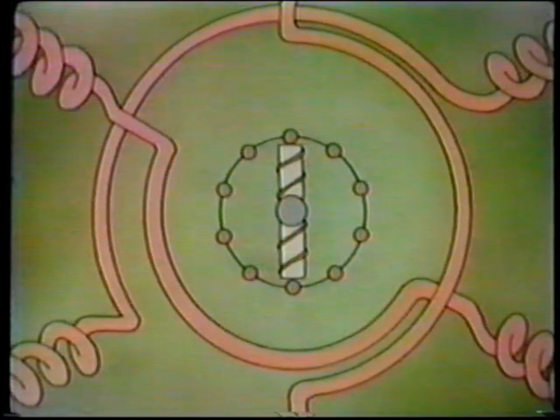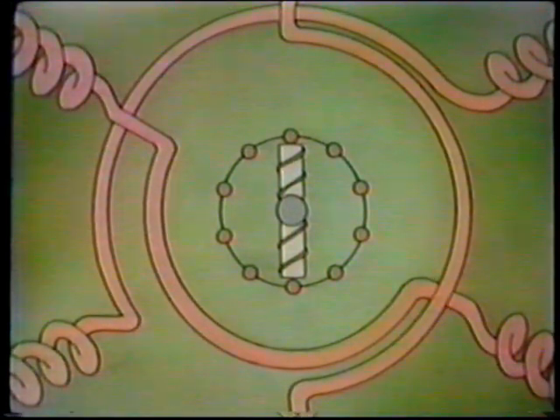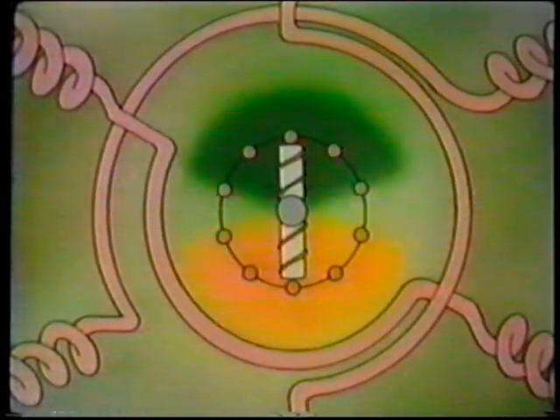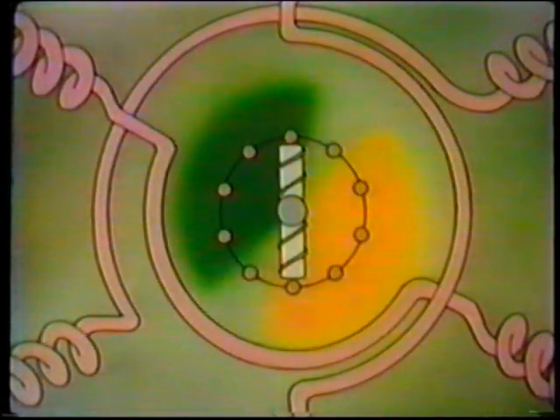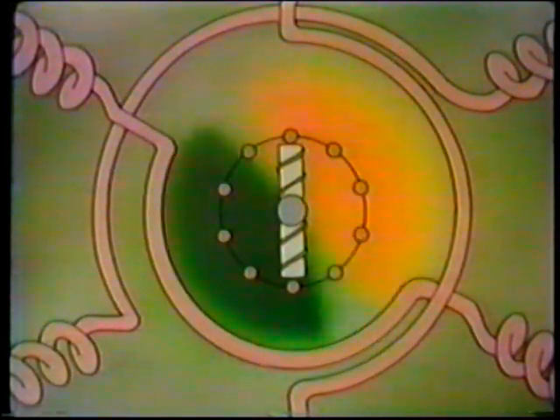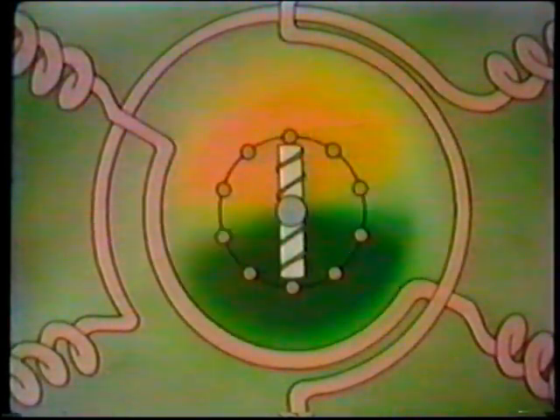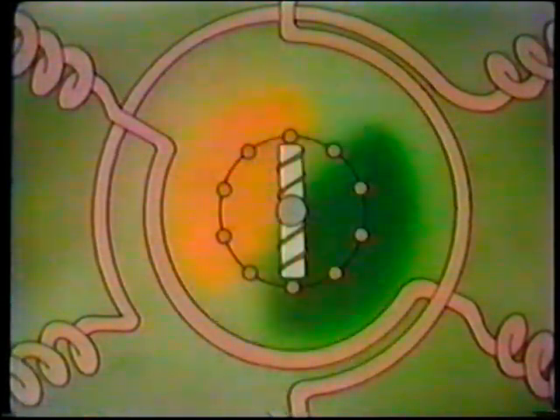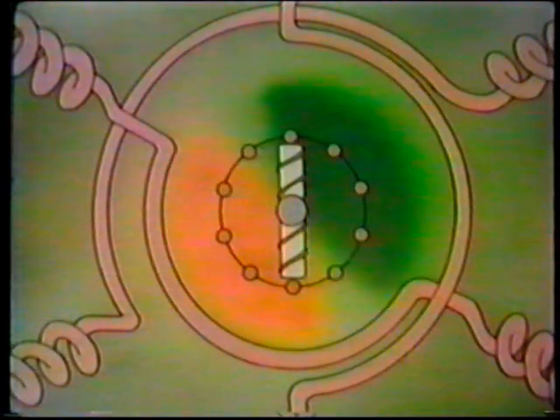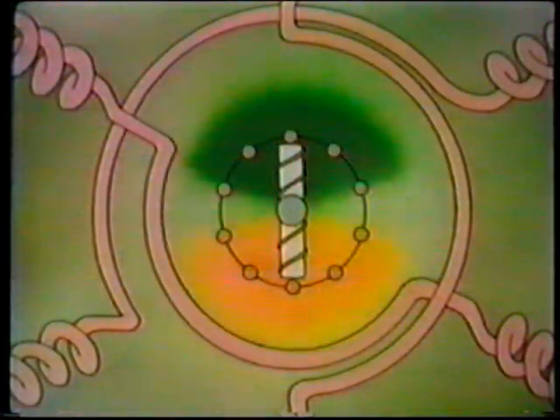Here's a simplified version of a rotor for a synchronous motor with amortisseur bars on it. When the motor is first started, the stator field immediately rotates at synchronous speed. The rotor, however, is unable to lock in with the stator's rotating field. But relative motion between the rotor and the stator's field causes a voltage to be induced in the amortisseur bars.